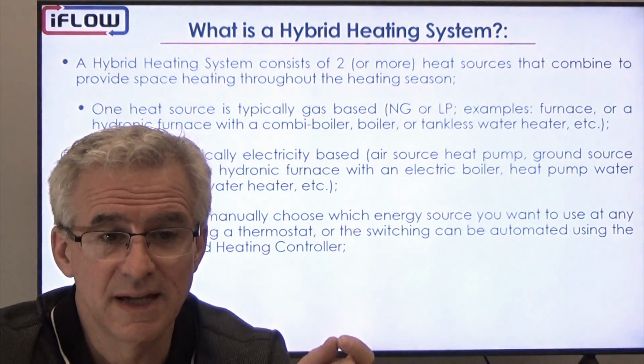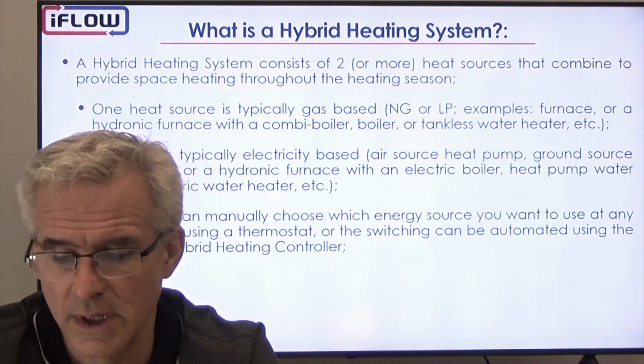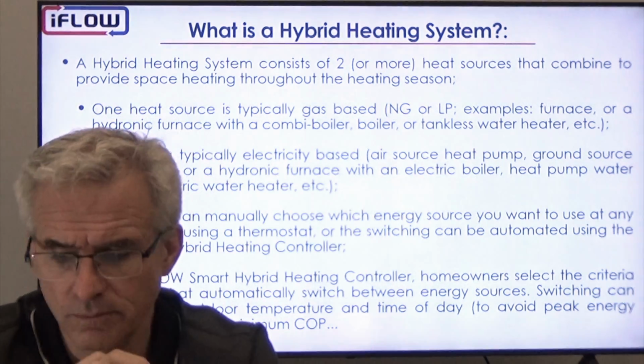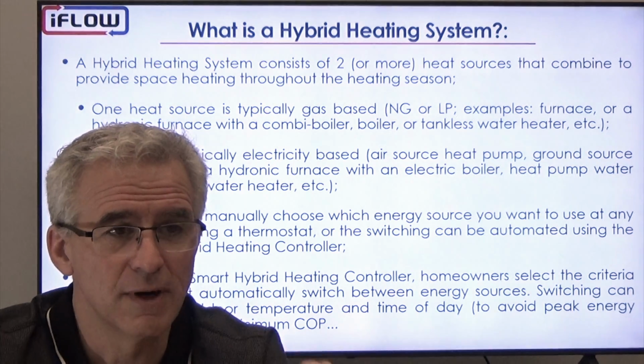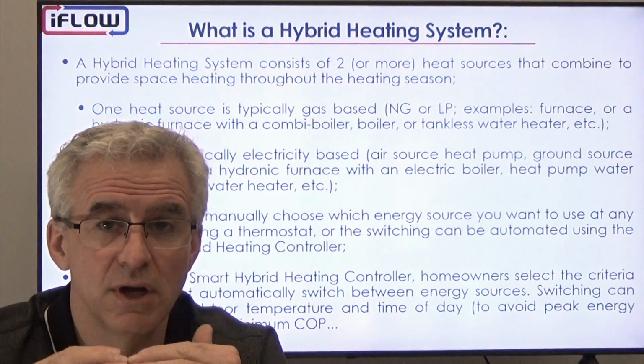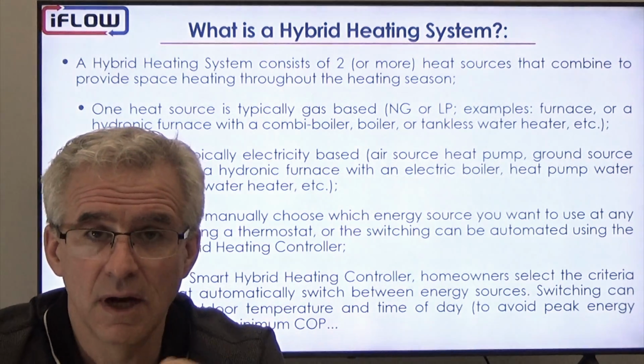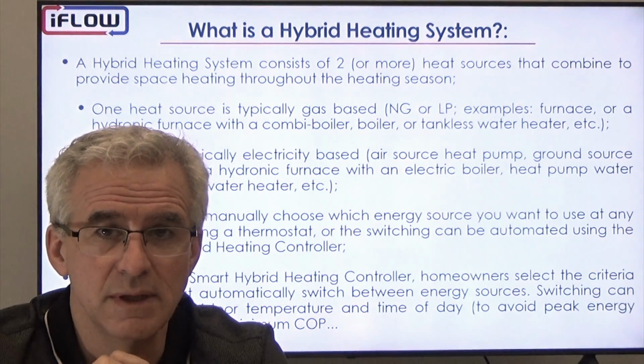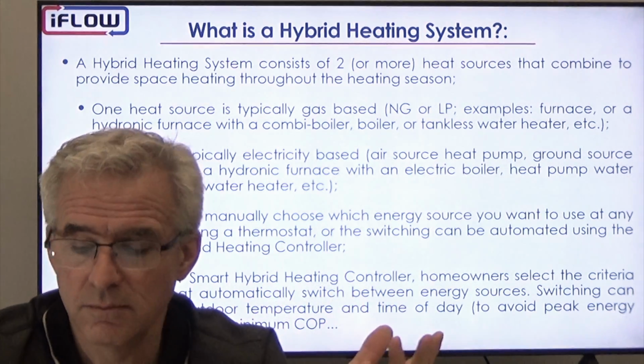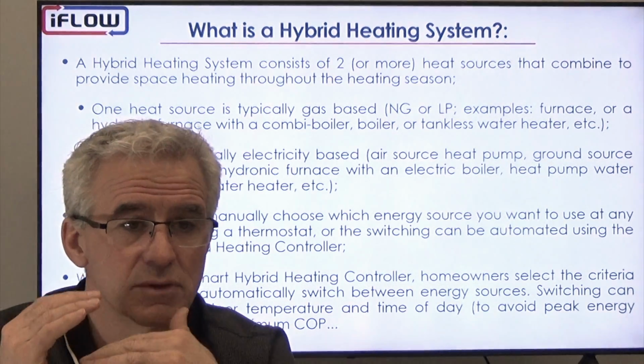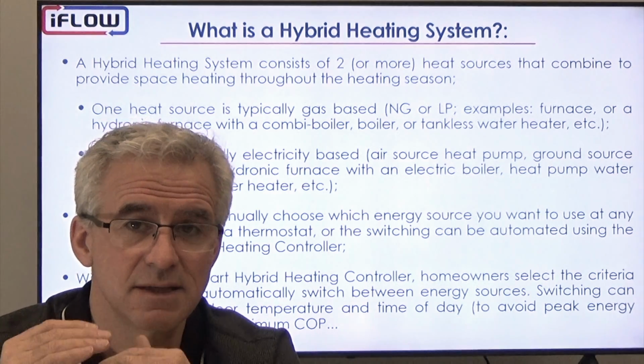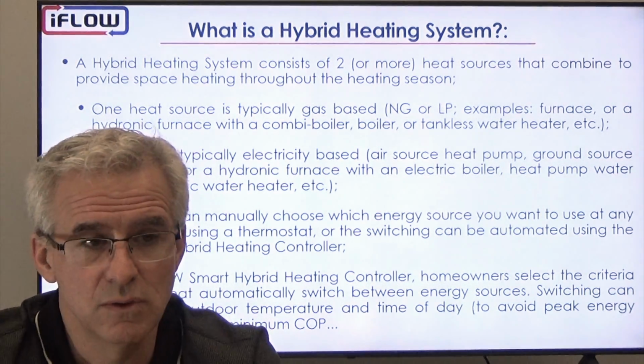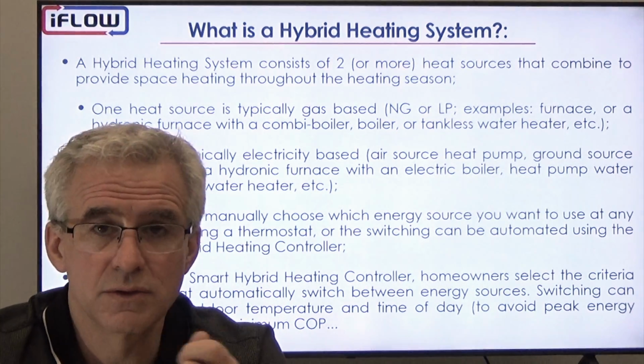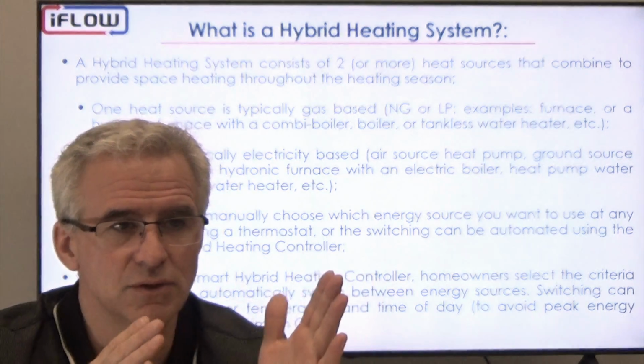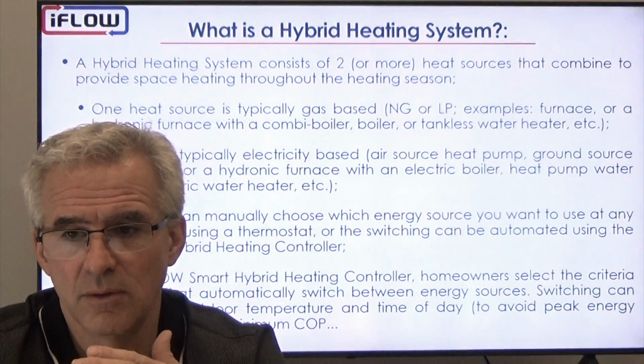Typically, that's done by the homeowner manually selecting at the thermostat which system they want to run. With the iFLOW Smart Heating Controller, though, the homeowners select the parameters or criteria they would like to use to set the switching automatically. And then the iFLOW controller will do it automatically, so there's no manual adjustment needed. Switching can be based on an outdoor temperature and then offset by peak loads. So if it wants to run the heat pump but it recognizes it's in a peak electricity period, it can avoid those to minimize the cost and optimize the performance. And it can also switch based on minimum COPs. So for example, you'd set a threshold that if the COP is less than 2, then we would run the gas backup. If it's above 2, then we would run the heat pump.